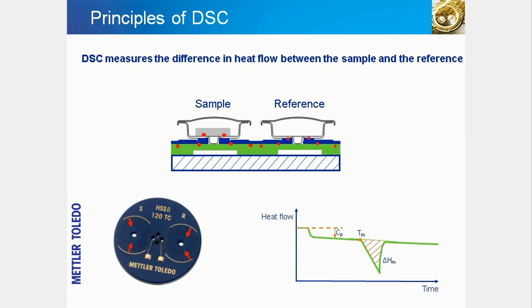The star shape is formed by the many thermocouples incorporated in the sensor. The thermocouples guarantee that the heat flow is accurately measured. The measurement curve shows a typical melting peak. The curve provides valuable information, such as the enthalpy of melting, the melting point, and the specific heat capacity.